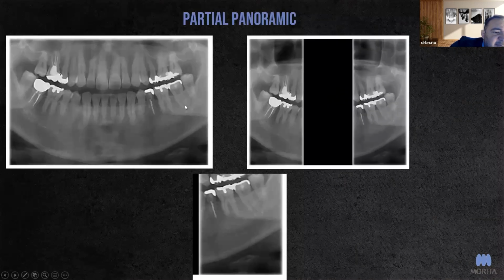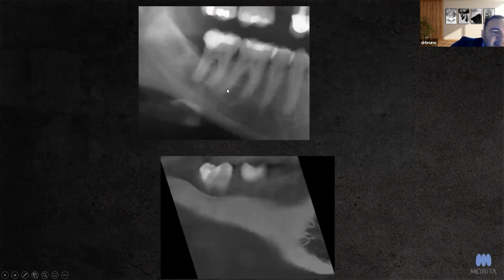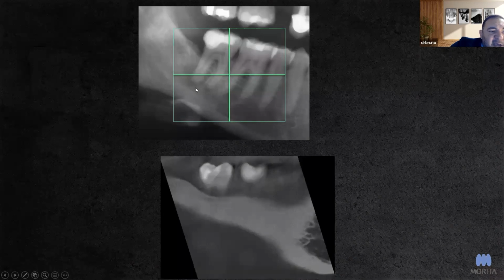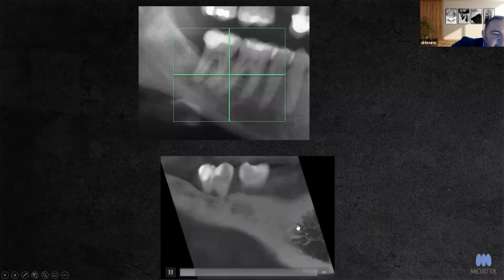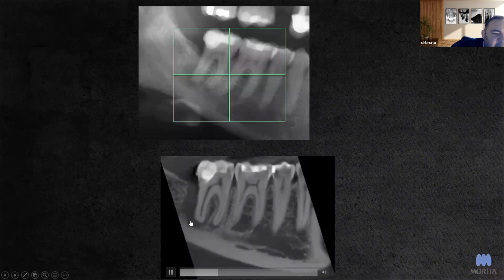So if you actually use the cropped images for Scout, they will also work. So here's a good example of a cropped panoramic image that we use as a Scout, and that actually works really well too. So do not fear not using the full pano if you just don't need it. Another component too is that if you wanted to see this canine here, although it's not on the image, I could actually move this line forward and scan the canine even though I don't see it, right? So the regions adjacent to the cropped panoramic images can also be imaged by using the box to aim at the area of interest here. You can see that you got exactly what we wanted.